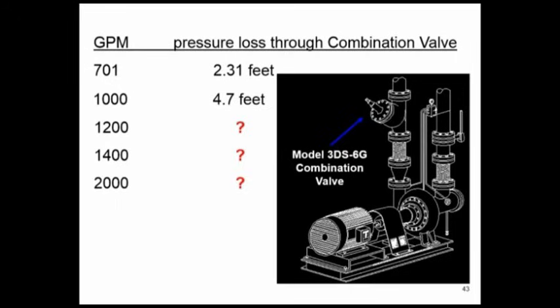I got 701 GPM is 2.31 feet. What should it be at 1,400? Should it be just about 4 times that? And sure enough, that's what it is. Now I've got all those pressure drops off of my system sizer from that one setting because it's fixed.